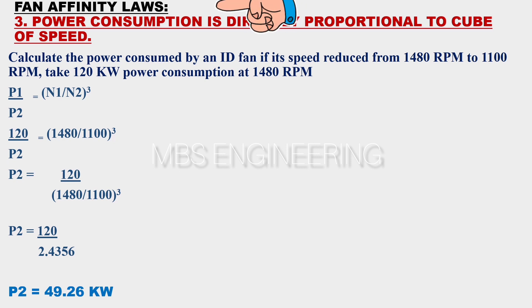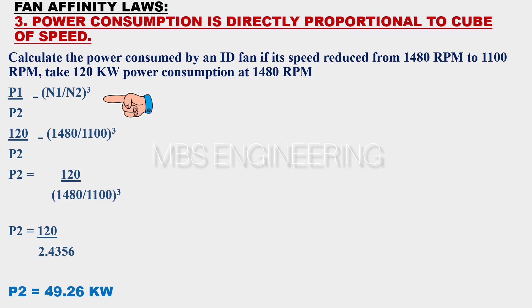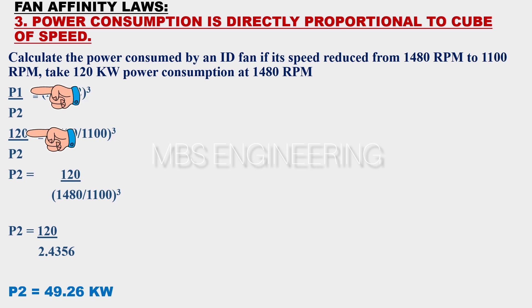Next, we learn the third affinity law and simple calculations. The third affinity law for fans: power consumption is directly proportional to the cube of speed. Calculate the power consumed by an ID fan if its speed is reduced from 1480 RPM to 1100 RPM, taking 120 kilowatts of power consumption at 1480 RPM. The power consumption P1 divided by P2 is directly proportional to the cube of speed N1 divided by N2, where P1 and P2 are power consumption in kilowatts. The given data: power consumption P1 is 120 kilowatts.